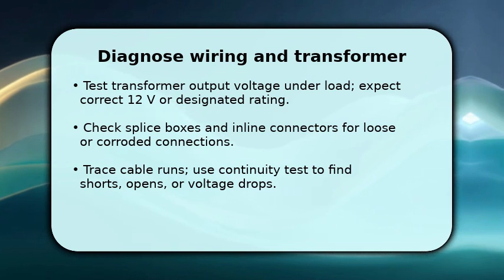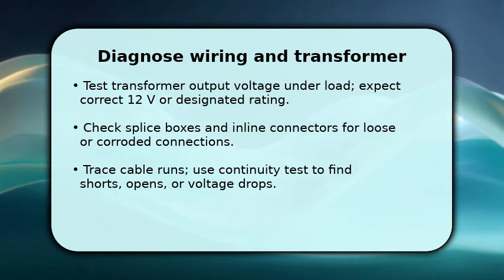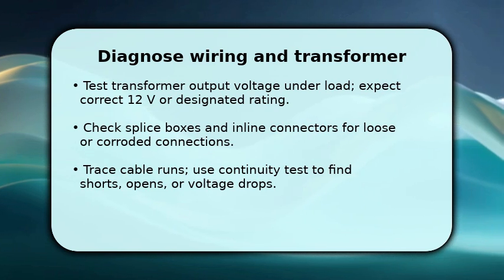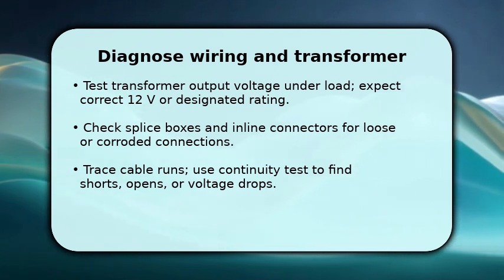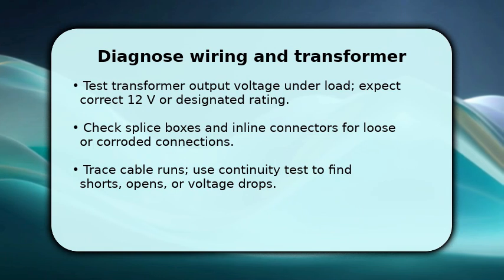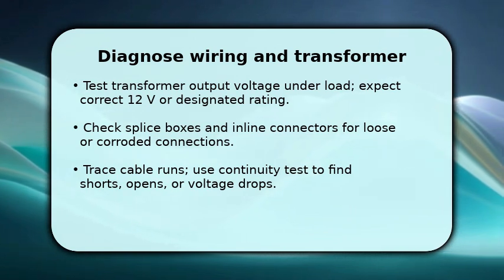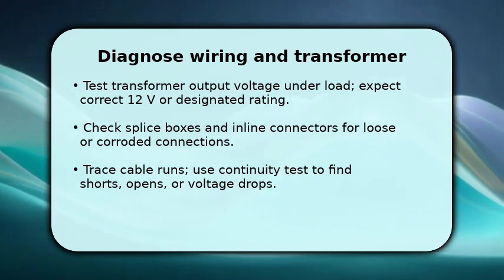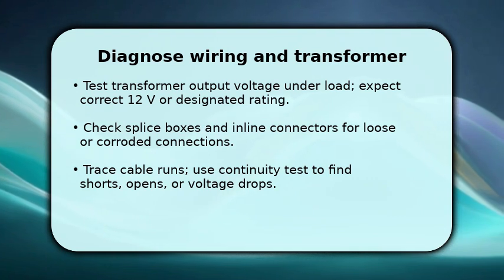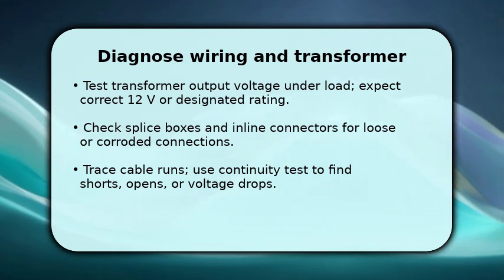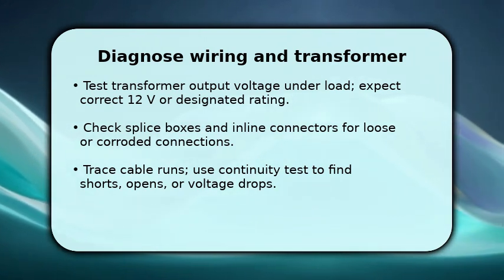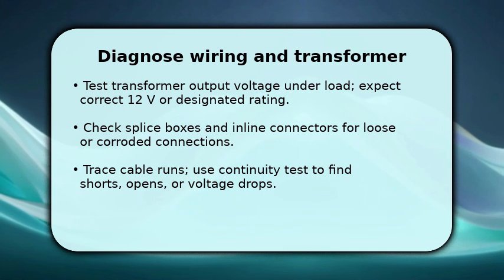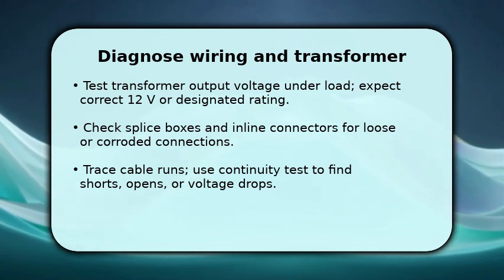Then inspect all splice boxes and connectors for loose screws, corrosion, or insect damage. Tighten or replace as needed. Once done, trace the low-voltage cable runs using continuity and isolation tests to locate opens or shorts. If you find a damaged run, cut back to solid insulation, resplice with proper connectors, and reseal with outdoor-rated materials.